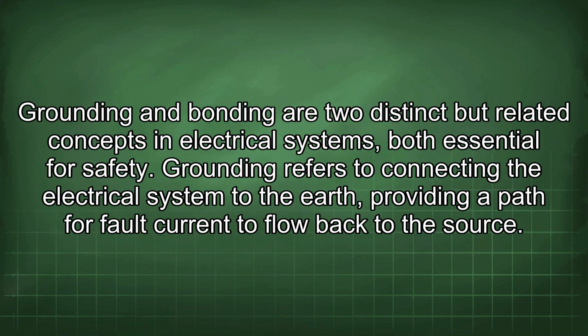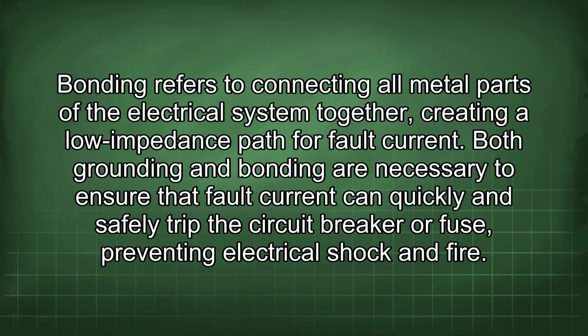Grounding and bonding are two distinct but related concepts in electrical systems, both essential for safety. Grounding refers to connecting the electrical system to the earth, providing a path for fault current to flow back to the source. Bonding refers to connecting all metal parts of the electrical system together, creating a low impedance path for fault current. Both grounding and bonding are necessary to ensure that fault current can quickly and safely trip the circuit breaker or fuse, preventing electrical shock and fire.